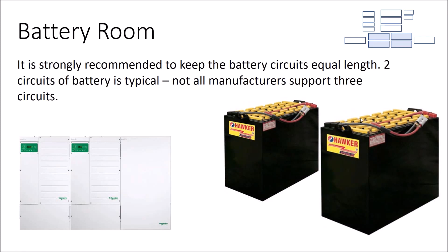I guess when you call up Schneider, they'll say, well, you could actually do 3 circuits of batteries. And we see some installers doing 3 circuits, but 2 circuits is recommended and 1 circuit is ideal. There's a lot of power that's going to flow through those batteries to that inverter. So you generally stick to 2 circuits of batteries in parallel.